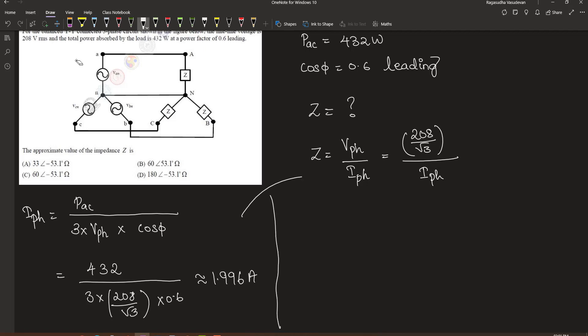Let us apply this here. The value of the impedance is equal to 208 divided by root 3, which is approximately 120.09, divided by the phase current. Therefore, the value of impedance will be 120.09 divided by 1.996. This is approximately equal to 60 Ohm.